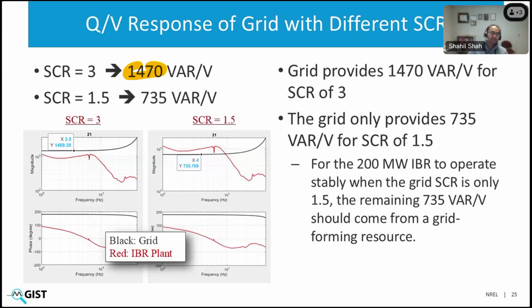Now, let's see how the SCR of 1.5 looks. The response becomes half, 735 VAR per volt. So for that 200 megawatt plant, if I want to make sure that it operates stably with this grid, there is a deficit of 735 VAR per volt that we need to supply to make sure that 200 megawatt IBR will remain stable for SCR of 1.5.